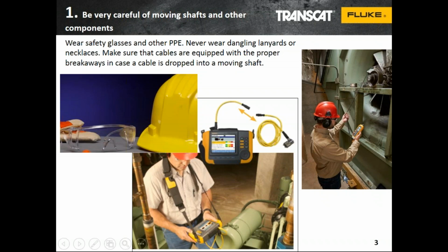And up on the right, you can see that this vibration meter has a long coiled cable - if that cable were to get wrapped around something, it's far enough away that you're going to have a bit of a safety buffer. Also, it will pull that cable out of the bottom of the meter instead of pulling the meter into the device with parts and pieces flying around.